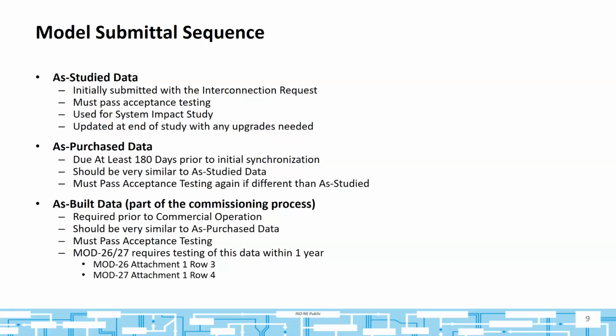Then as we're approaching synchronization, there is the as-purchased data submittal, which is, while not yet fully in service, expected that the generator can provide a set of modeling information for what was purchased and is being installed. Then the as-built data, part of the commissioning process, required prior to commercial operation, expected to be similar to the previous submittals and consistent with that. We do have model acceptance testing that we push this through, aligned with NERC standard MOD 26, 27 voltage response and frequency response modeling standards.